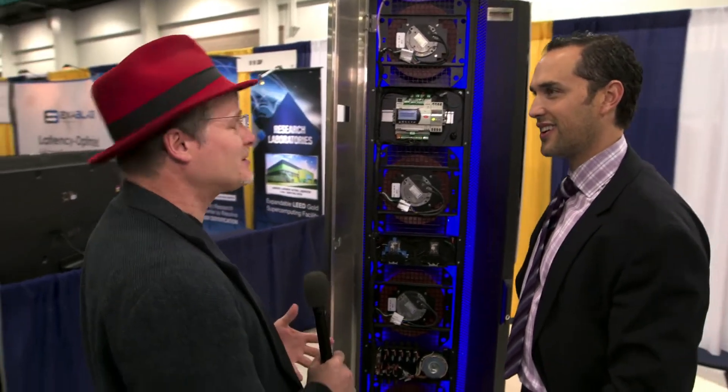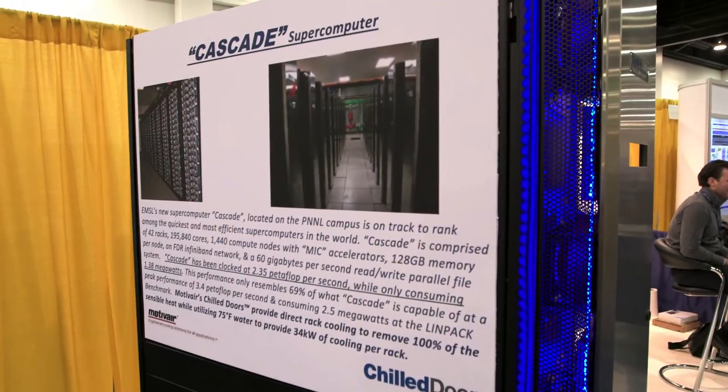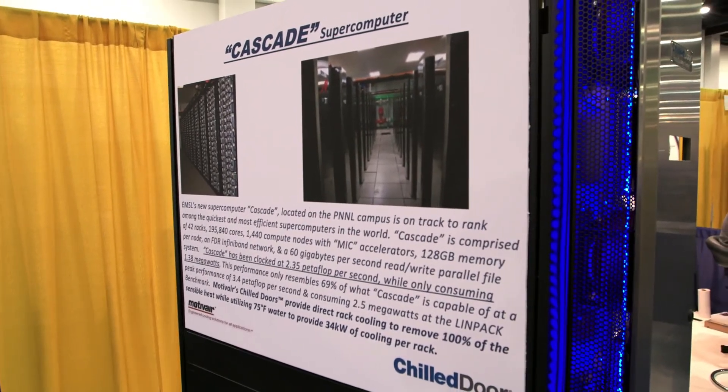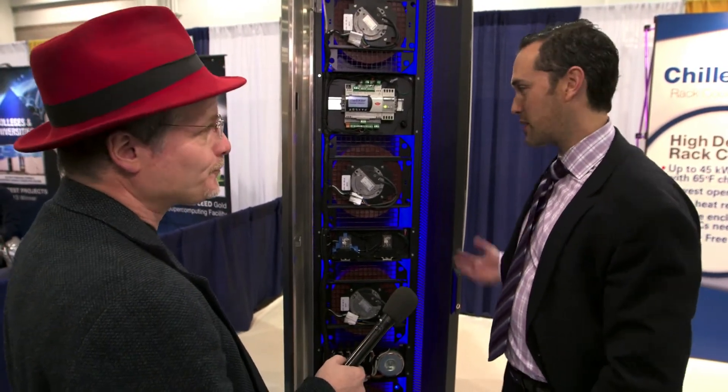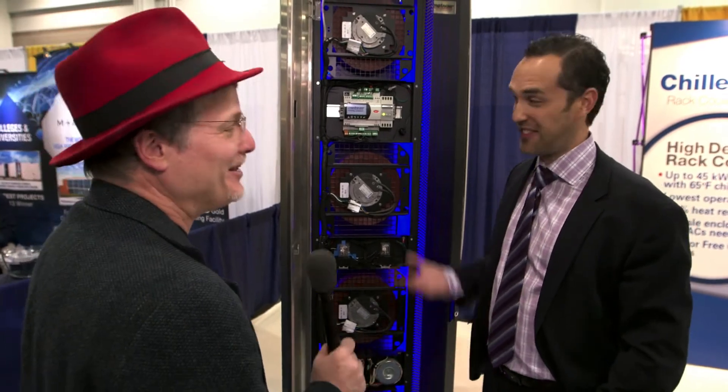This looks like it's for a big cluster. Do you have any recent deployments you can tell us about? This year we just deployed on Cascade, which is PNNL's new cluster up in Washington State. It's pretty impressive — there are 48 racks of gear operating at about 34 to 38 kilowatts per server rack. It's a big machine, nearly 200,000 cores. They got all that into a standard 42U by 600 rack, and then the next challenge was cooling it. They're looking for a high-efficiency cooling method — they actually feed our chilled doors from a naturally occurring aquifer that's underneath the facility, so they're not even really paying for chilled water. Chilled water is free, and then they feed it to the doors.